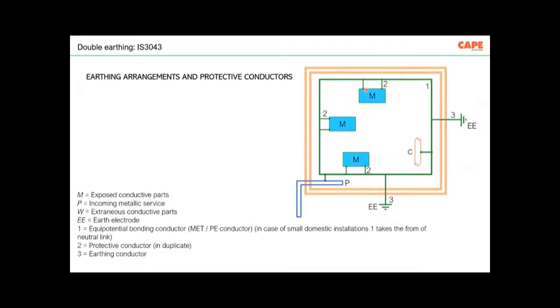Three-phase equipment or larger equipment are supposed to have two connections in duplicate. You can see here two protective conductors in duplicate. So larger equipment are supposed to have two connections to the protective equipotential bonding, and this is called double earthing. This double earthing has nothing to do with two earth pits in soil. So double earthing means the exposed conductive parts of class 1 larger equipment are connected to the protective equipotential bonding with two connections. That is double earthing.